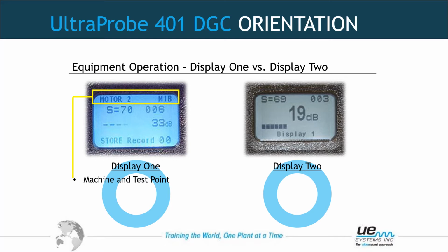Motor 2, motor inboard bearing. Motor 2 is the machine or location name. MIB, motor inboard bearing, is actually the test point name. S equals 70. This is the sensitivity setting, which ranges from 0 to 70, 70 being the highest. This normally flashes when you can adjust it. It is also the resting or home spot for the sensitivity dial.